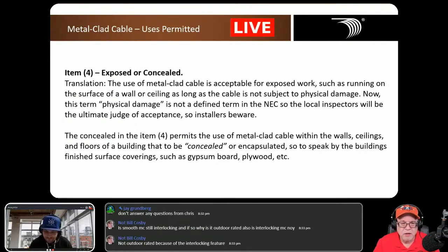Number 4, exposed or concealed: the use of metal-clad cable is acceptable for exposed work, such as running on the surface of a wall or ceiling, as long as the cable is not subject to physical damage. Interesting tidbit: MC cable has to meet a crush and impact rating of 1,000 foot-pounds, or if it's over 2 gauge and larger, it has to be 2,000 foot-pounds of crush and impact. Tray cable has to meet that exact same crush and impact standard.